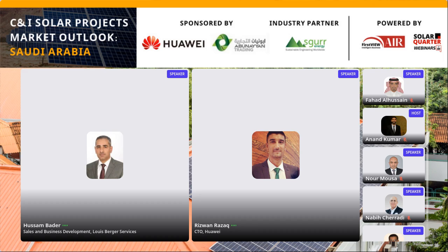Sure, thank you. So the current range of inverters are now all supporting both standard monofacial modules and bifacial modules. But the key difference is the current that will be produced from the PV modules and strings that are connected using bifacial modules. Specifically, as the rear side gain increases the current further, the inverter needs to accommodate for that and ensure there is sufficient available input current within the inverter itself, so that even if that current is high, the inverter would not clip it, or the limit of clipping would typically occur at the MPPT level.